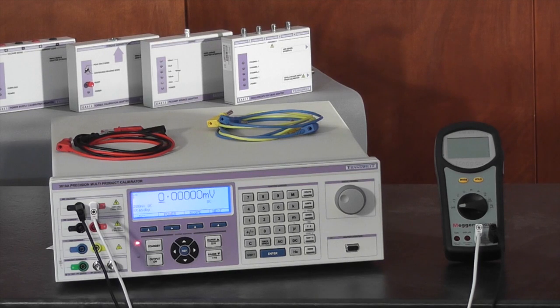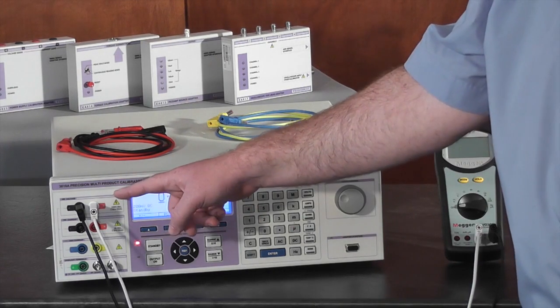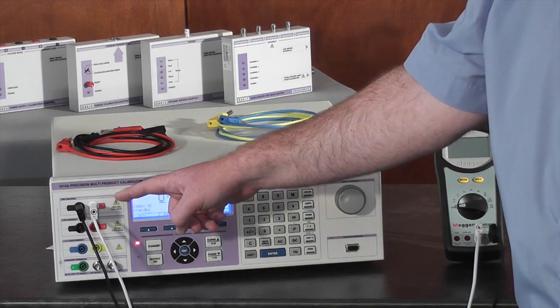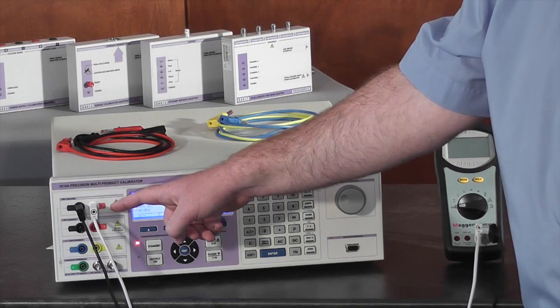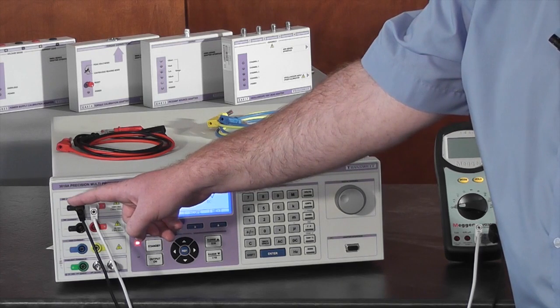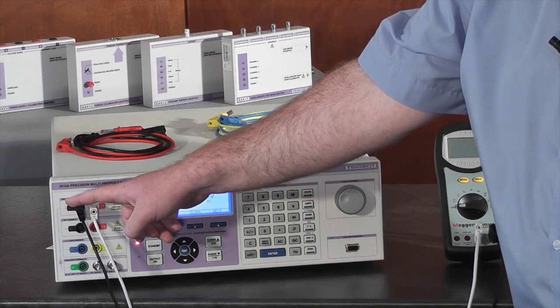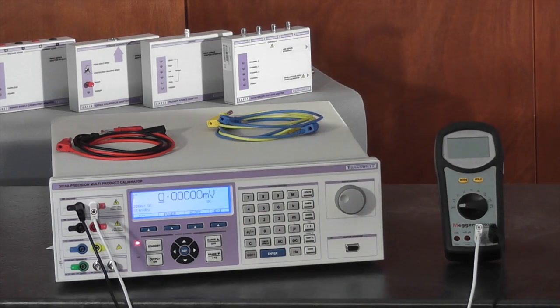The first function we will be calibrating is the voltage input. Connect the multimeter to the voltage terminals on the 3000A. The 3000A's voltage terminals are color-coded and the active output indicated with an LED to enable simple connections.